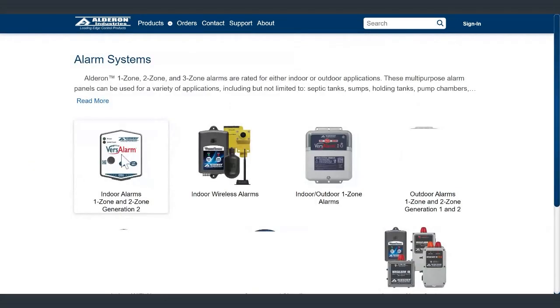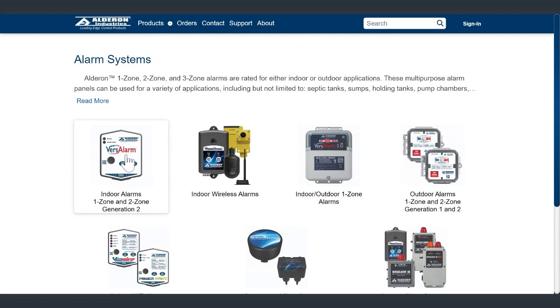So for alarm systems, we have our standard indoor alarms, and we have 1 zone and 2 zone available with that. They come in a small package like that. We have an indoor wireless alarm, which technically is a wireless float system. The float is connected to the yellow transmitter, and that transmitter transmits a signal up to a quarter mile away to the alarm, which has a receiver on it. So if you don't want to go underground and bury cable for your control float to sound the alarm, you can send that wireless signal just from the float action to the alarm.